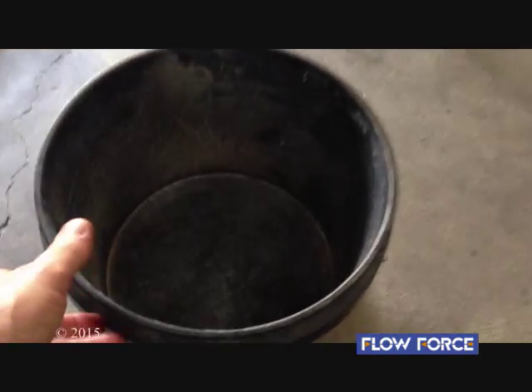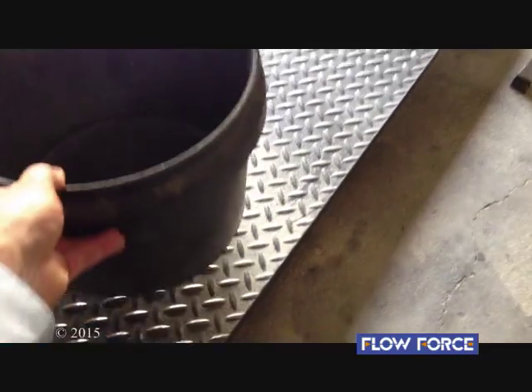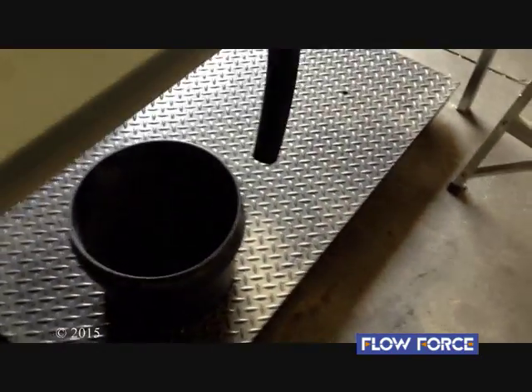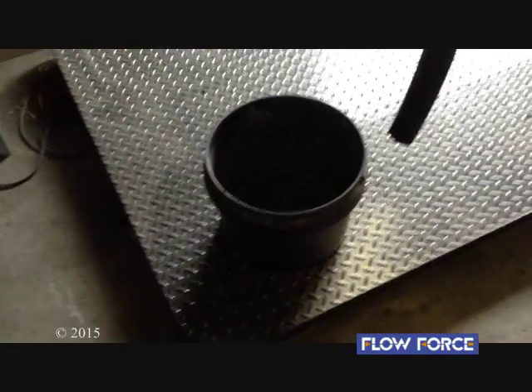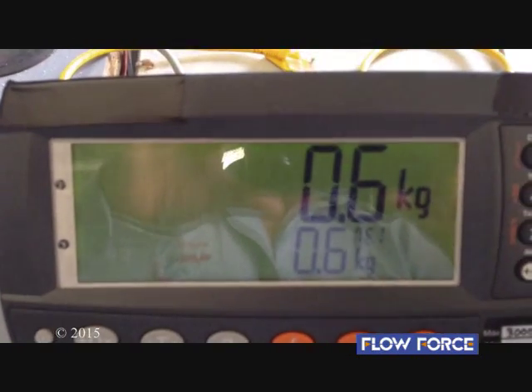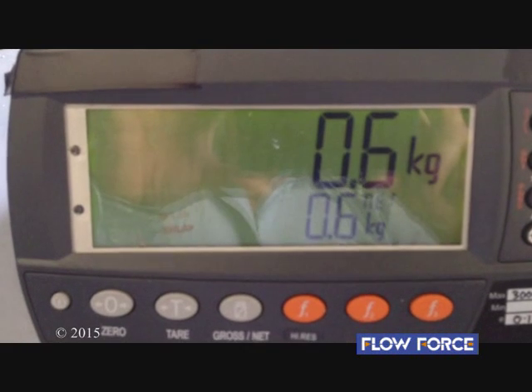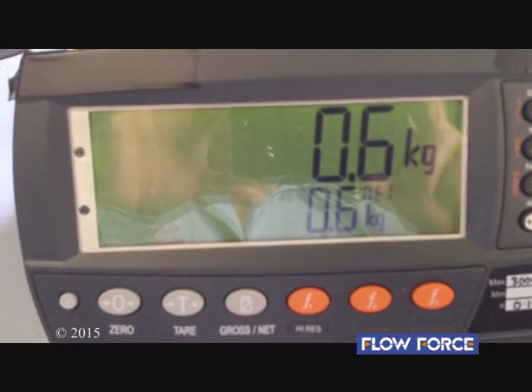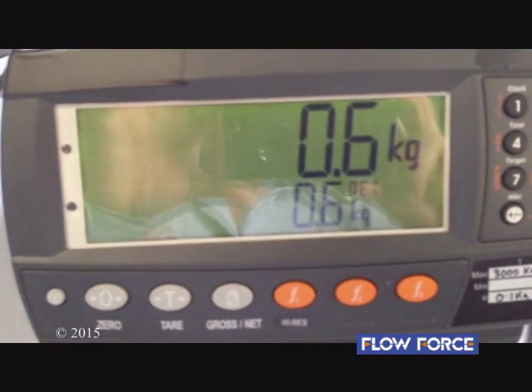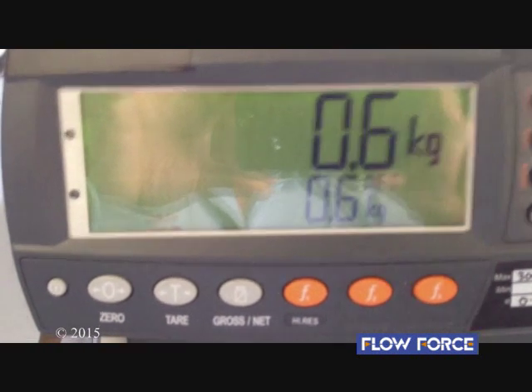So the first thing we do, we'll put the test weight and check the weight of our test receptacle. In this instance here, you'll see it's 0.6 of a kilogram. We'll take this and mark it on our calibration sheet and begin the setup for the rest of the testing.